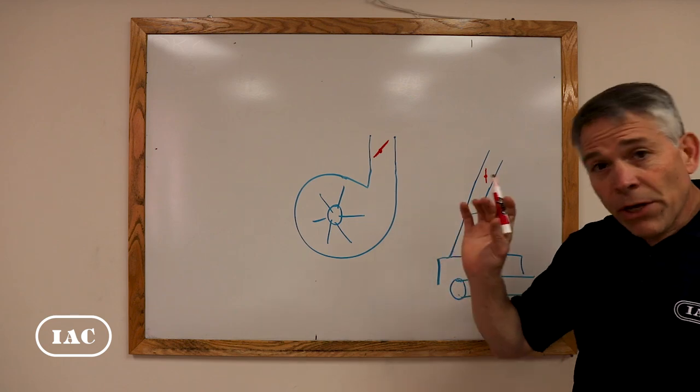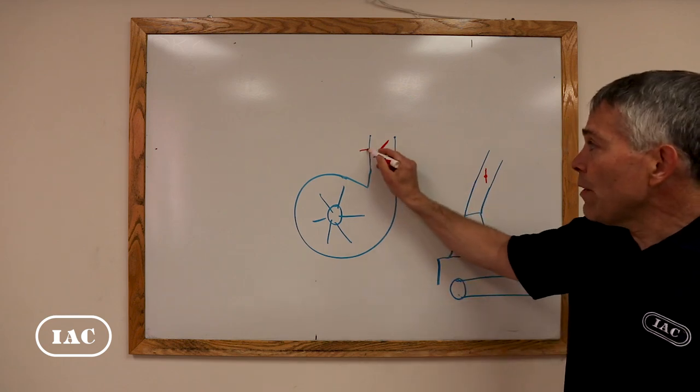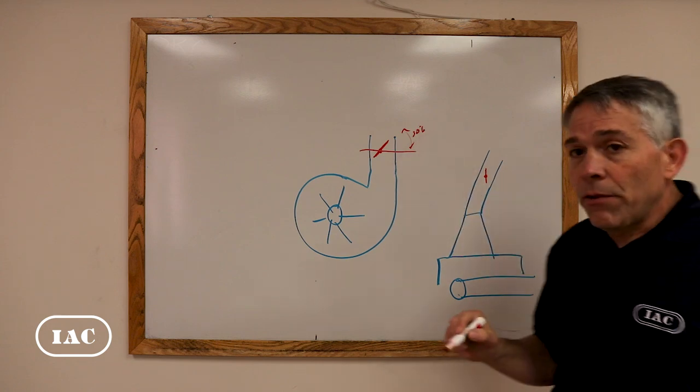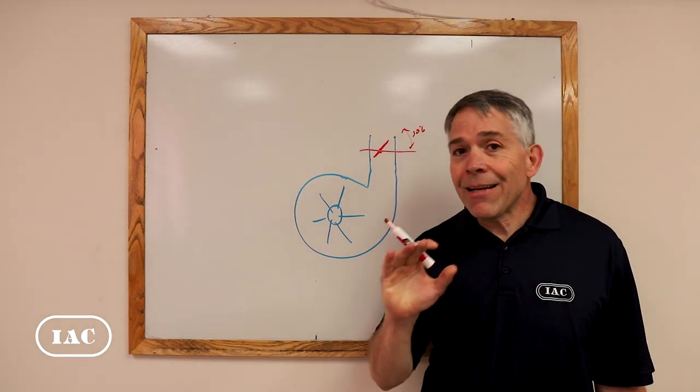But butterfly dampers are very quirky, meaning that if you see this in a position of 30%, people think that you're getting 30% of the flow and that is not the case.